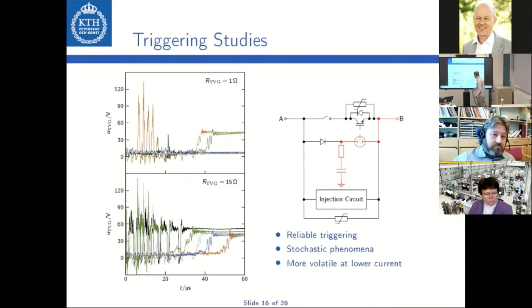In the next step, we studied the commutation from the main path to the commutation path. Here in the first slide for the original configuration. In the initial state, the main path of the EAR DCCB conducts. This you can see with the blue current in the beginning, which corresponds to the LCS current. Then the triggered vacuum gap is triggered. This causes the RC circuit to discharge into the triggered vacuum gap, which gives this RC-like current in the triggered vacuum gap, which is the red line.